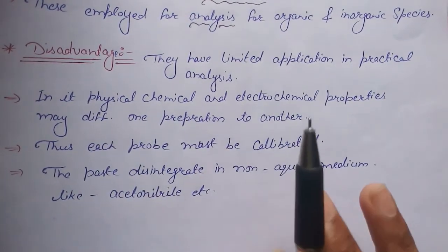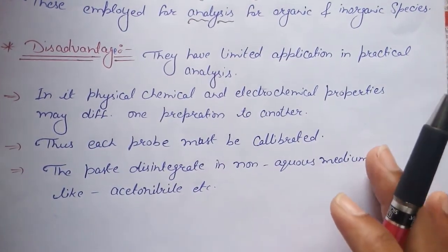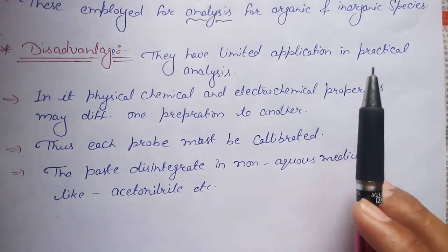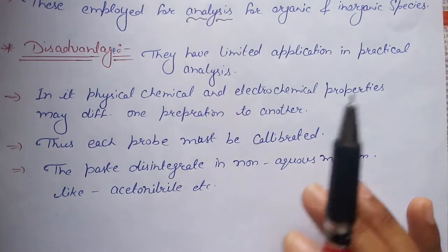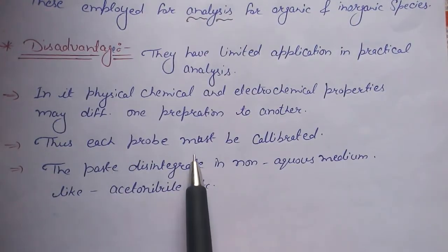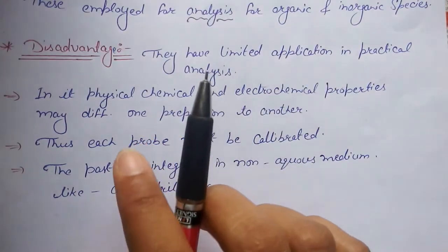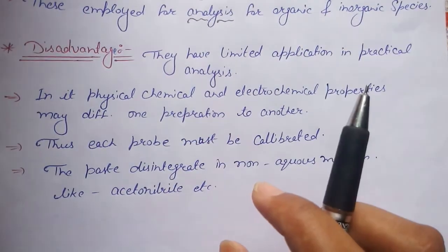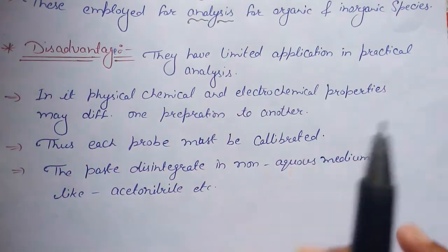It means in every preparation you have to work with a different formation. Its physical, chemical or electrochemical properties will differ in different practicals. Thus, each probe must be calibrated. Every time, you have to calibrate it properly before use.